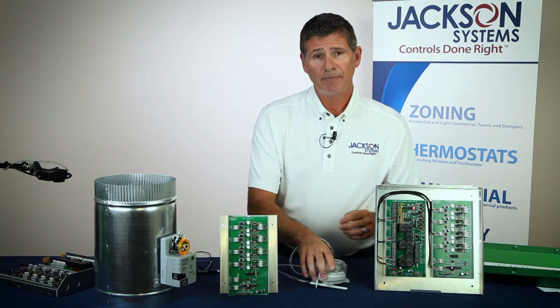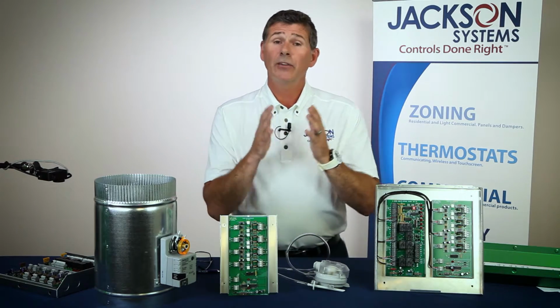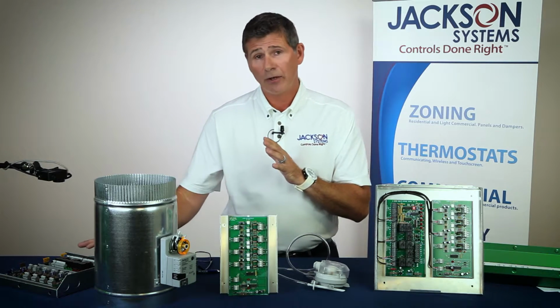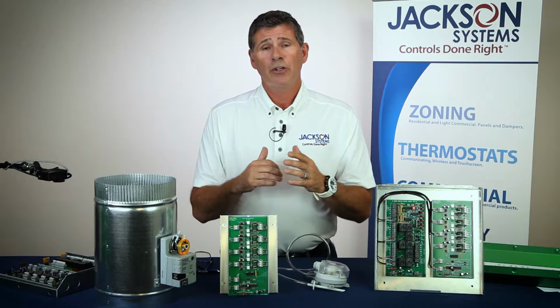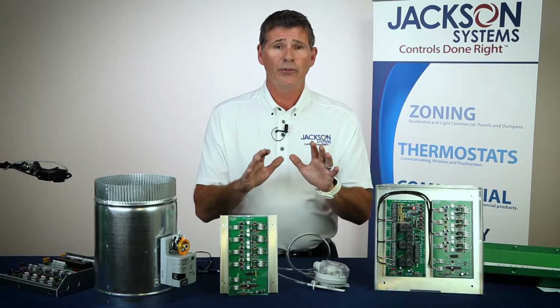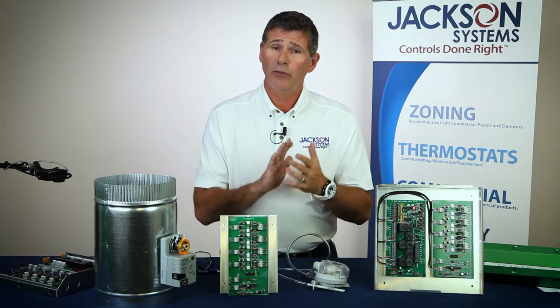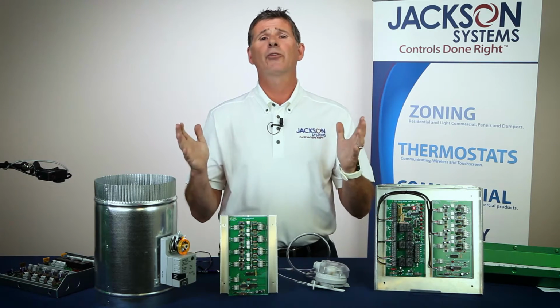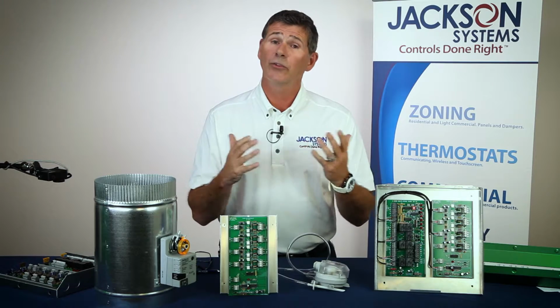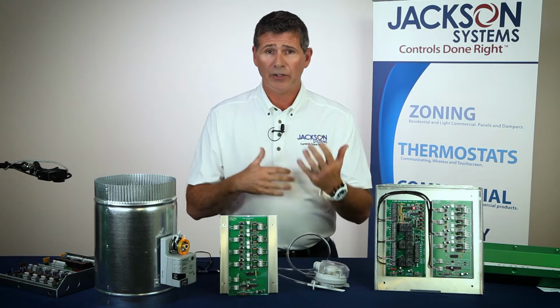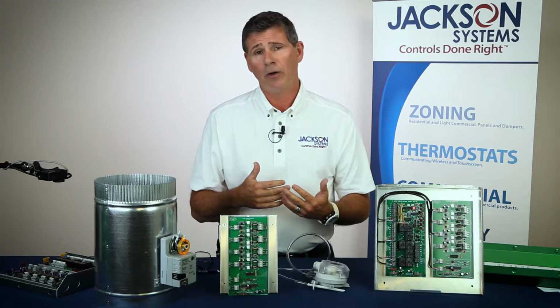Well, quite simply, I want you to think of it this way. If you have a 3-zone system, just like this panel set up on my right over here, you've got 3 dampers in the system, you have 3 thermostats. So all the dampers are open right now simply because all the zones are satisfied. So the fan is running and it's circulating air throughout the home.